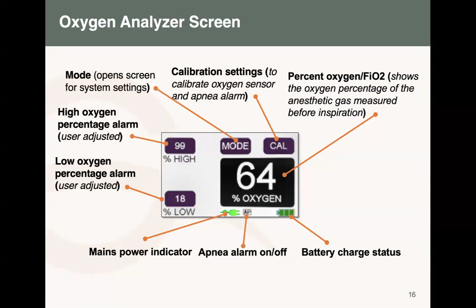So this is the display. It has mode and calibration setting. It displays the percent of oxygen, but also shows the alarm, the higher and the lower level, which will alarm when you go beyond this limit. Since I think all of you know this, I won't spend much time on it. Next. The most important thing is calibration.